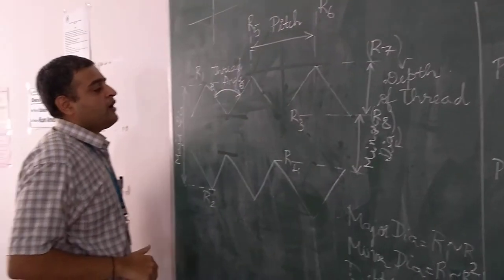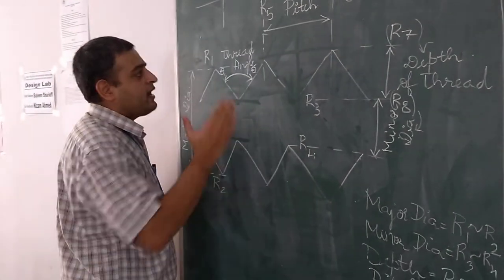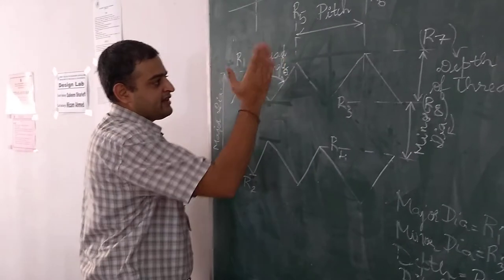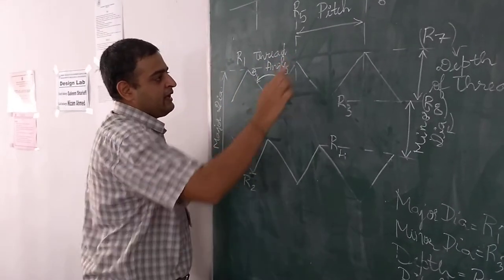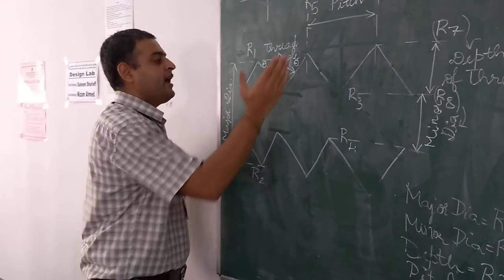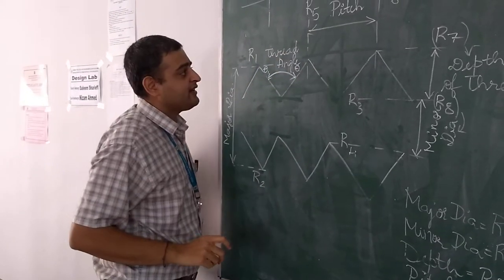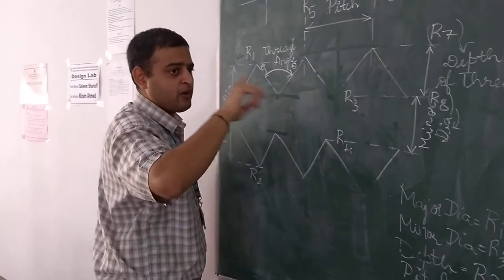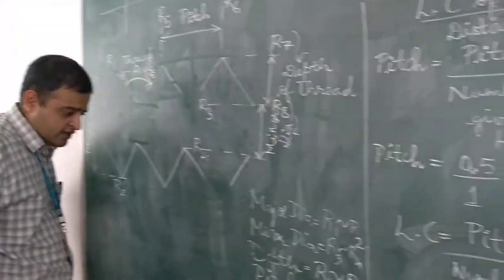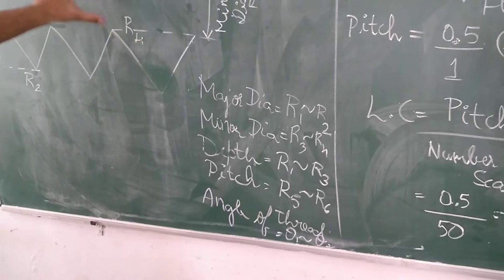There is also a circular scale to calculate the thread angle. The cross wires can be made coincident with the thread flanks, and you can calculate the thread angle on the circular scale provided on the optical projector. These are the important parameters and formulas, and using this diagram we can relate them.